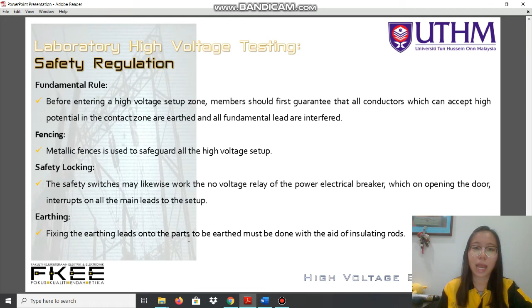Next, the fencing. The metal fence is used as a safeguard for the high voltage setup. Next, the third one is the safety lock. The safety switching may likewise work the no-voltage relay of the power electrical breaker, which on opening the door, interrupts all the main leads to the setup. Next, this is the very important part, which is the earthing. Fixing the earthing lead onto the part to be earthed must be done with the aid of insulating rods. The earthing rod is used to discharge all the equipment which contains the high voltage.